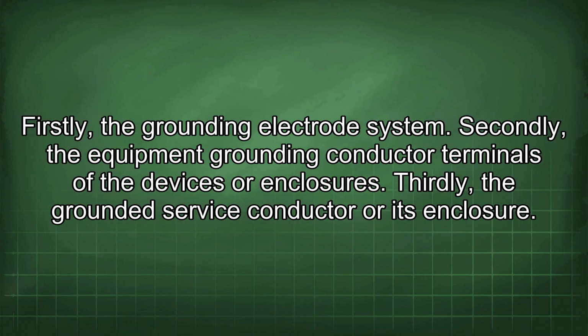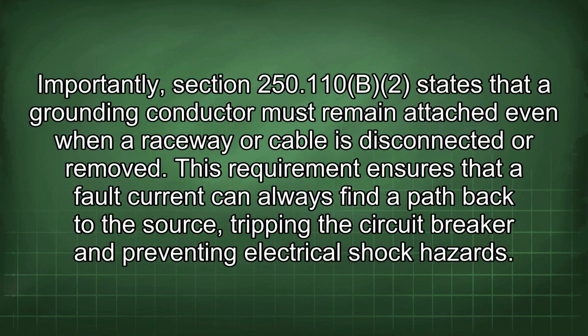Firstly, the grounding electrode system. Secondly, the equipment grounding conductor terminals of the devices or enclosures. Thirdly, the grounded service conductor or its enclosure. Importantly, Section 250.110b states that a grounding conductor must remain attached even when a raceway or cable is disconnected or removed.